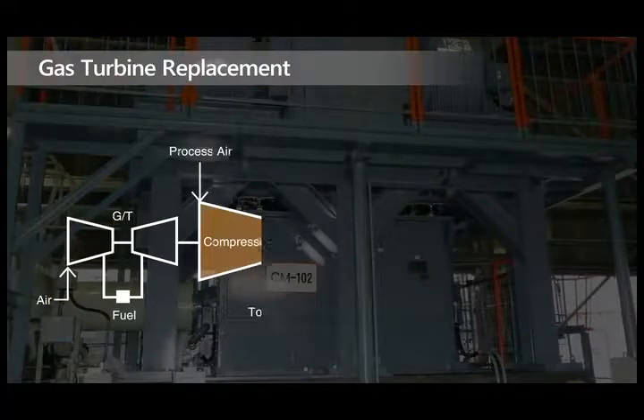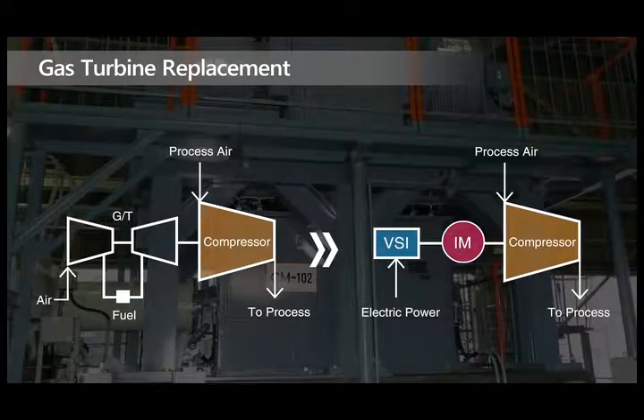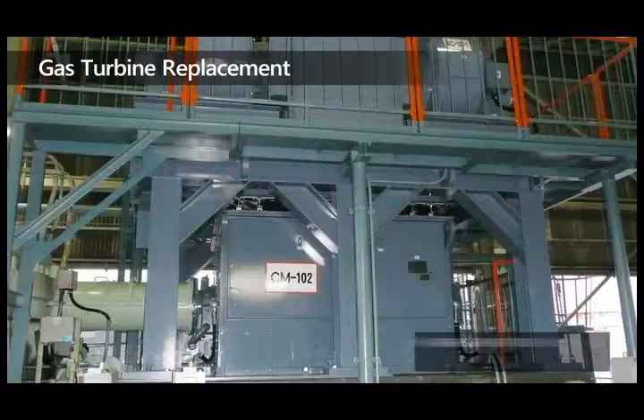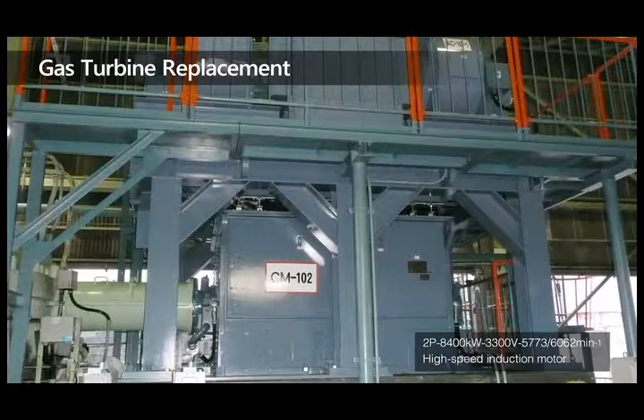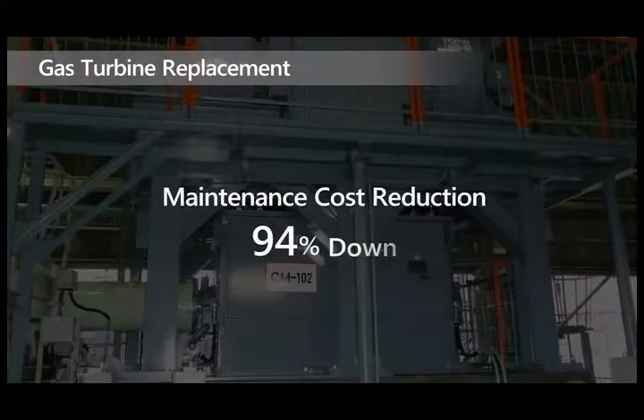The second example is a gas turbine replacement project in Japan. Another Japanese company successfully reduced greenhouse gas emissions and also freed itself from the trouble of obtaining obsolete gas turbine spare parts and poor technical support to maintain the turbine. The motor rating was 8,400 kilowatts and 5,773 rotations per minute. According to the customer's evaluation, maintenance cost was reduced by as much as 94%. MTBF of the turbine driver system was 4 years, while that of the electric motor driver system is 15 years.